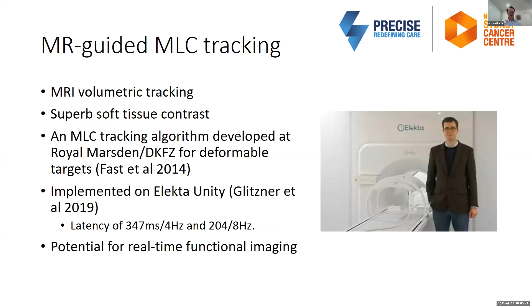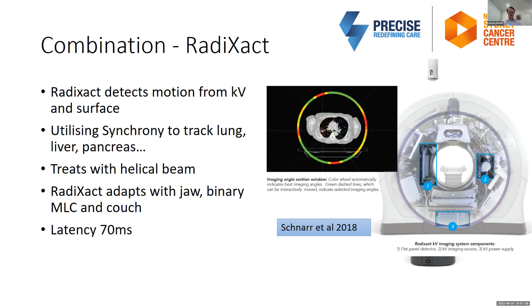So we then also have the RadiXact system. RadiXact is sort of the modern version of tomotherapy, also from the CyberKnife company. This system is on a ring bore gantry, so it's able to rotate very quickly. It has a binary multi-leaf collimator in there. The RadiXact system detects motion from the kV images and surface, very much using the CyberKnife Synchrony system on a standard sort of linear accelerator framework. And it adapts to motion using the jaw, the binary MLC, and the couch in combination, with a very small latency.